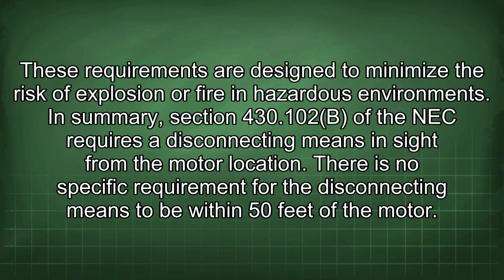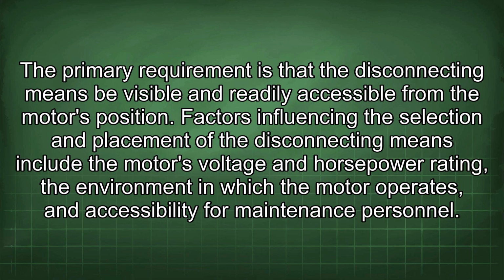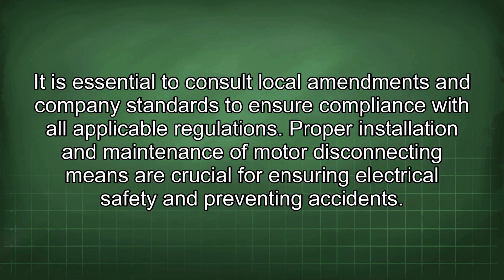There is no specific requirement for the disconnecting means to be within 50 feet of the motor. The primary requirement is that the disconnecting means be visible and readily accessible from the motor's position. Factors influencing the selection and placement of the disconnecting means include the motor's voltage and horsepower rating, the environment in which the motor operates, and accessibility for maintenance personnel. It is essential to consult local amendments and company standards to ensure compliance with all applicable regulations.